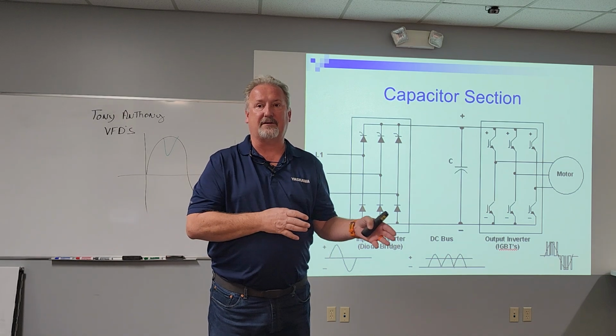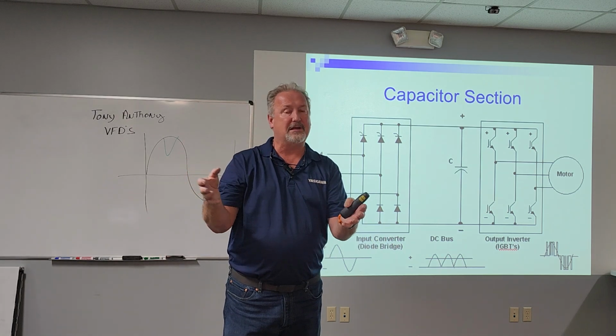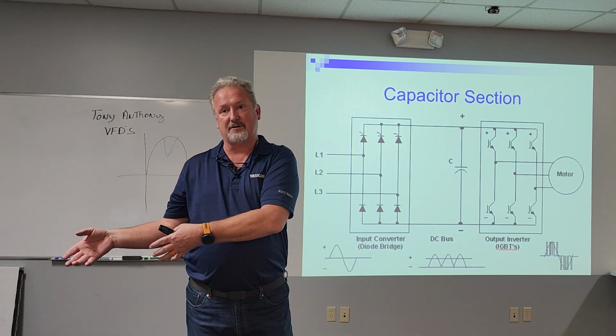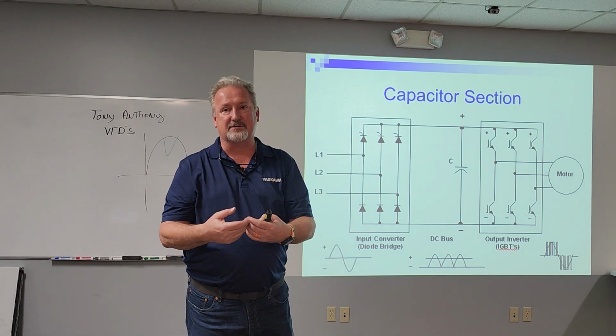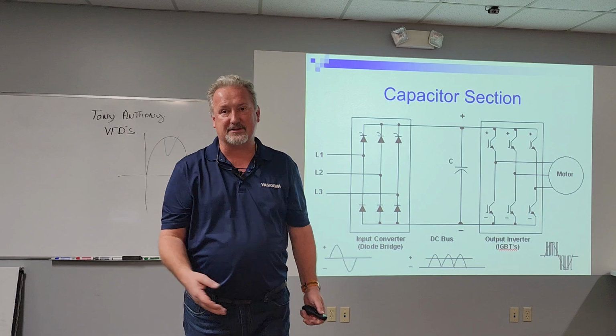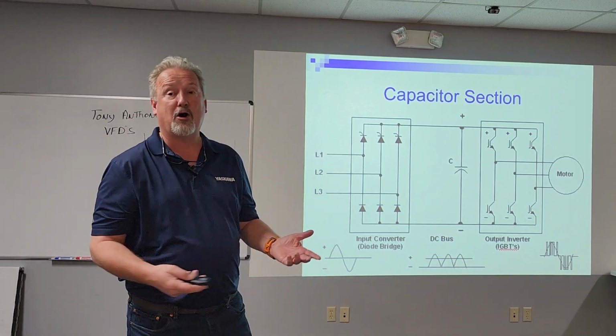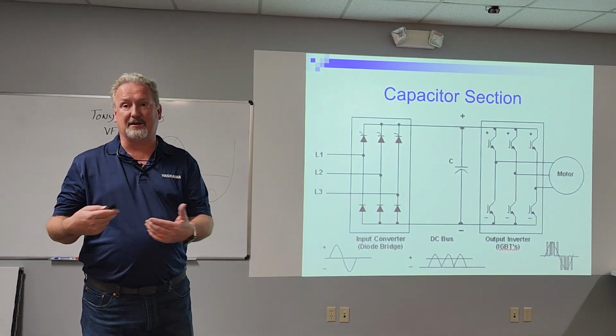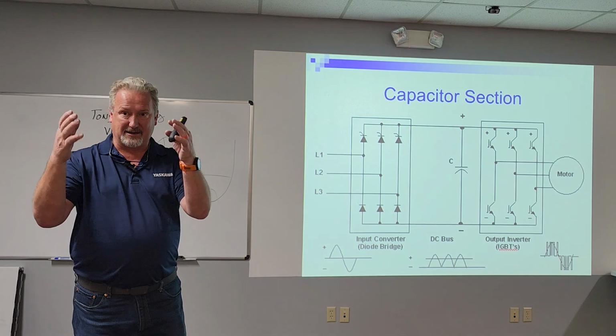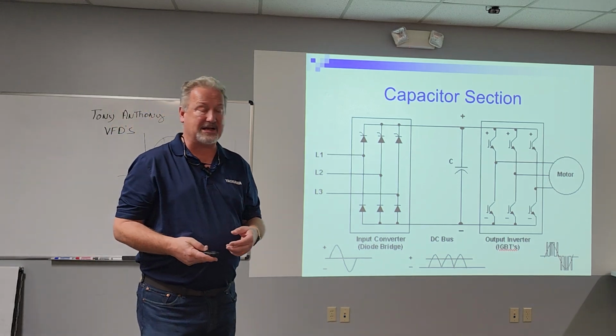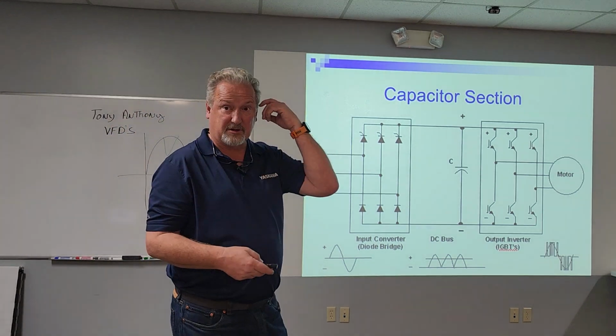It's just the cost effectiveness. If you have to replace a whole module, it might be time to replace the drive, whereas if you can just replace the capacitors, it might be cost effective. So it really depends, but it's not hard to do. You just have to know how, and there's a procedure for the capacitors and such. Same thing with the IGBTs, we'll talk about that a little bit.